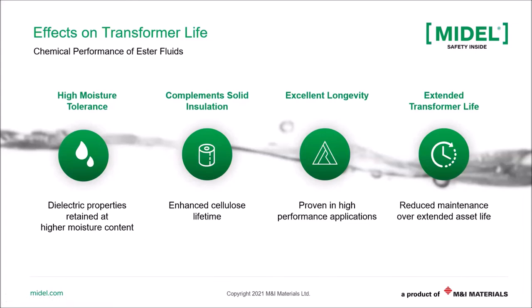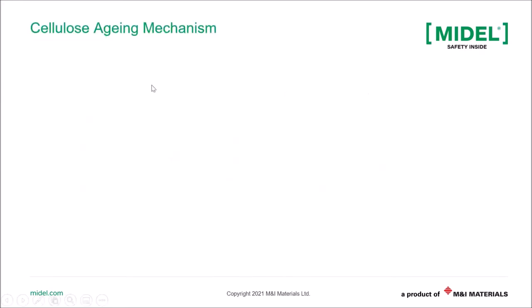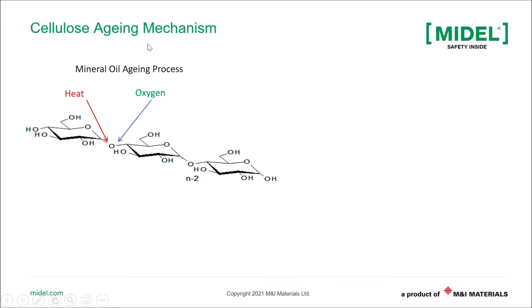The higher moisture saturation capability of the ester liquid allows the cellulose material to age slower, hence it improves the life of the insulation in the transformer, and it also allows the insulation system to operate at higher temperatures. And I'll explain this in the next slide. So in this slide, what I want to show you is what the aging mechanism of cellulose is inside the transformer. When you think of a transformer, it has many things in it, but the key components are the insulating liquid. It has the conductor, which is typically either copper or aluminum. It has the core steel, and as far as the windings are concerned, they're usually held in place by the solid insulation, which is typically cellulose material.